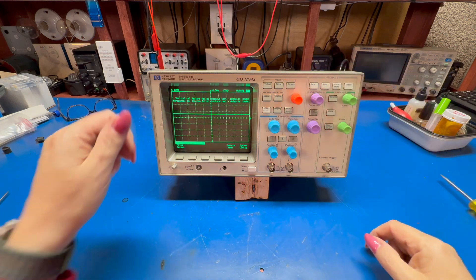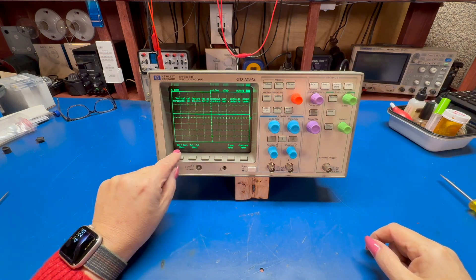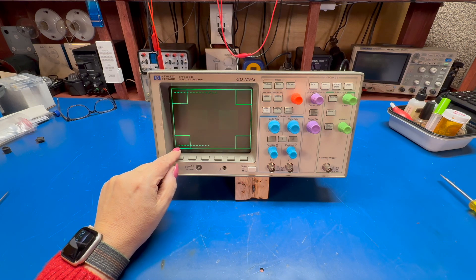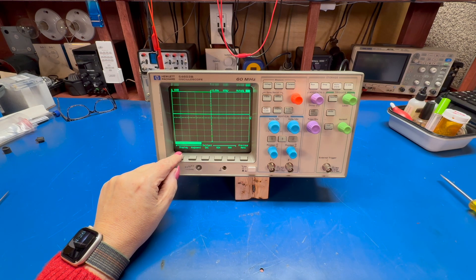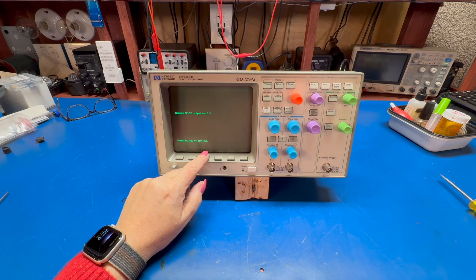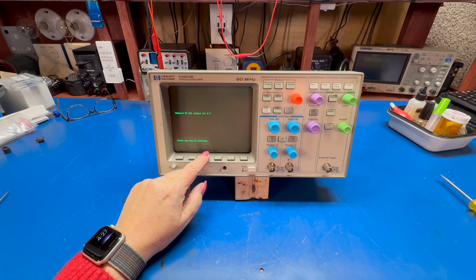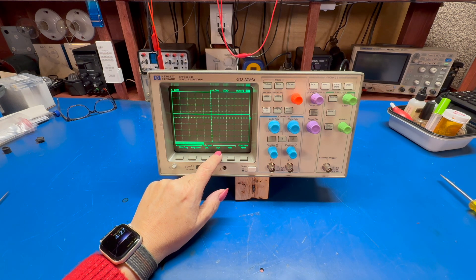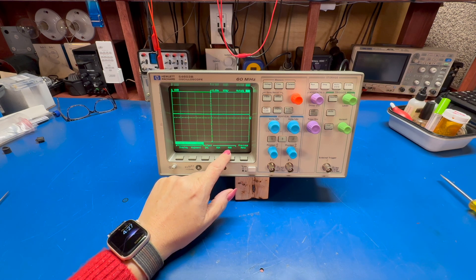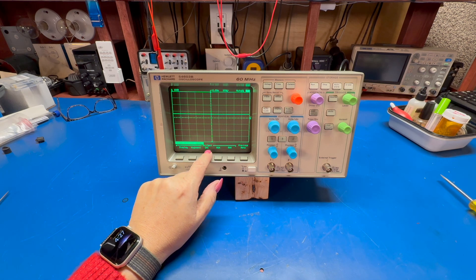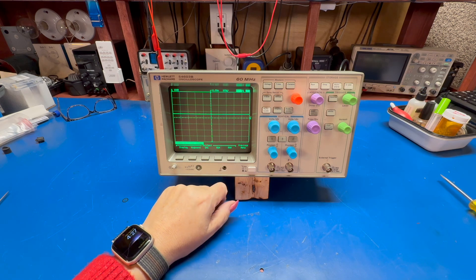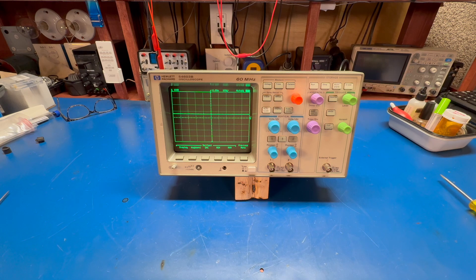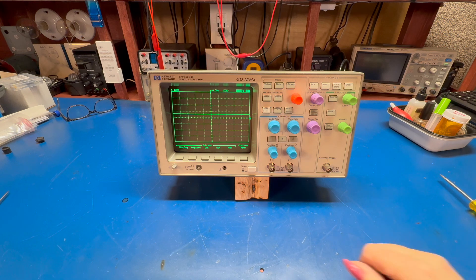Let's go to utility, service, self-test, display. That looks good. Measure DC cal output for zero. Let's see, ROM scope self-test passed, RAM self-test passed. Okay, so looks like the RAM module is probably okay, but I killed all the calibration data.